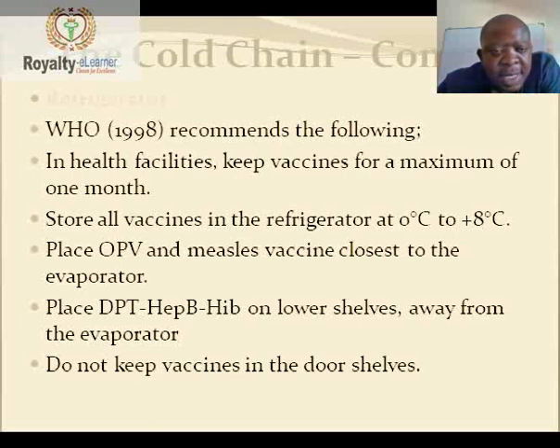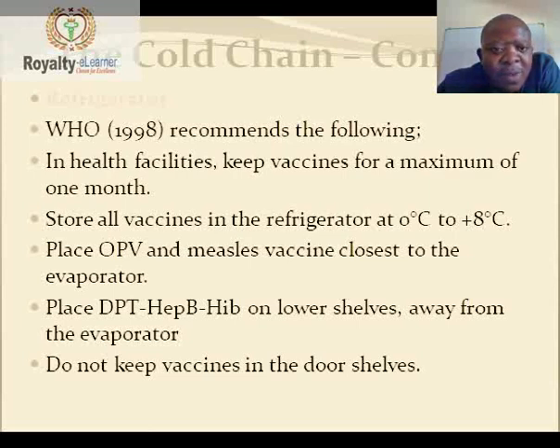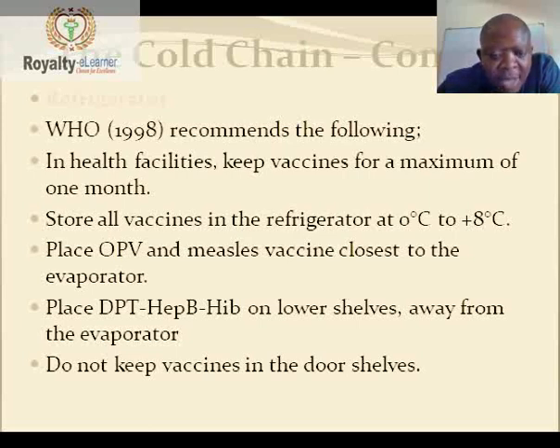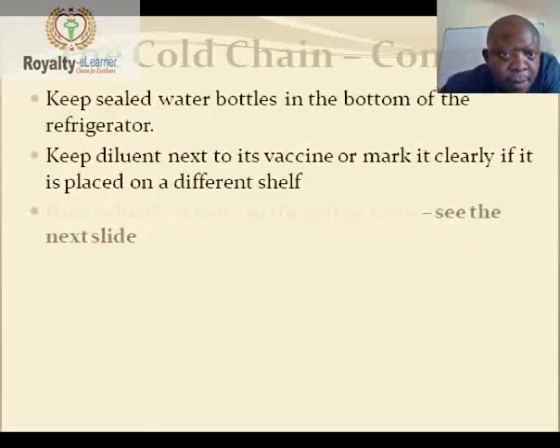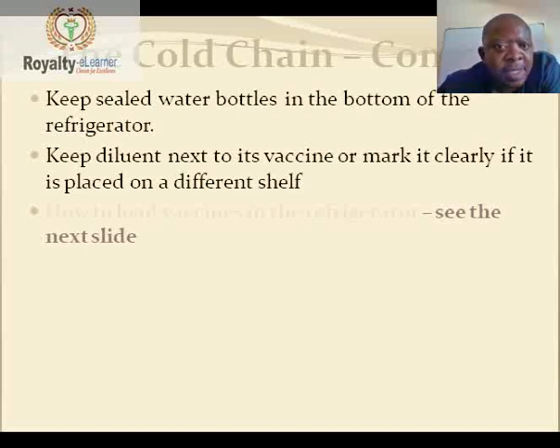The WHO in 1998 recommends that in health facilities, vaccines are kept for a maximum of one month. Store vaccines in the refrigerator at 0 to positive 8 degrees Celsius, placing OPV and measles vaccine closest to the evaporator, placing DPT on lower shelves away from the evaporator, and not keeping vaccines in the door shelves. Keep sealed water bottles in the bottom of the refrigerator and keep diluent next to its vaccine or mark it clearly if placed on a different shelf.